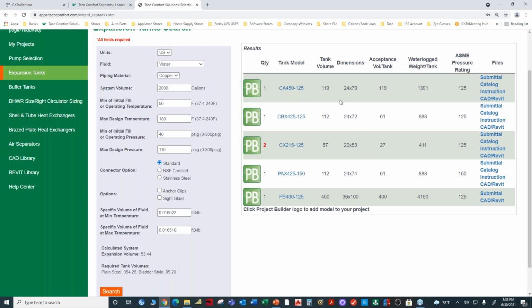Yep. And let's assume for a moment that you pick this first one, a CA 450-125. Again, the 125 is the pressure rating of the vessel, and 450 liters converted into gallons is 119 gallons. Now you install it in the building and everything is up and running.